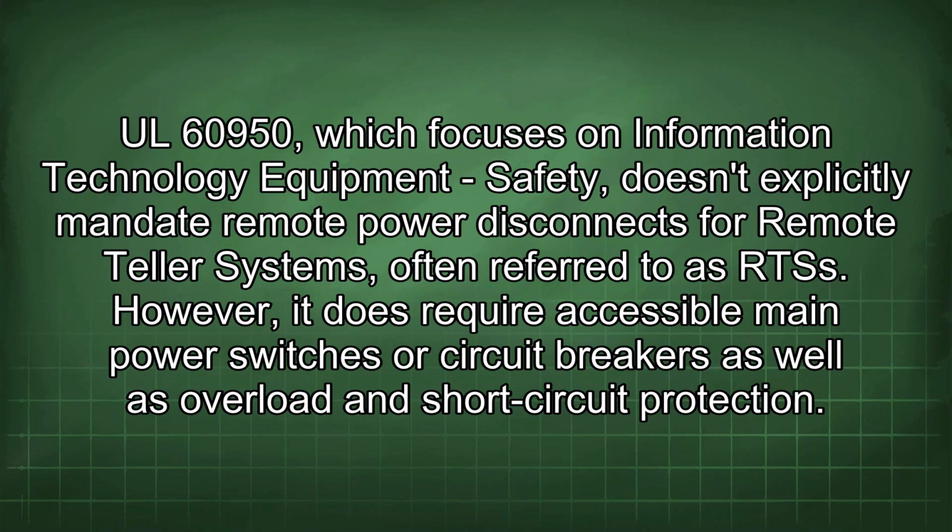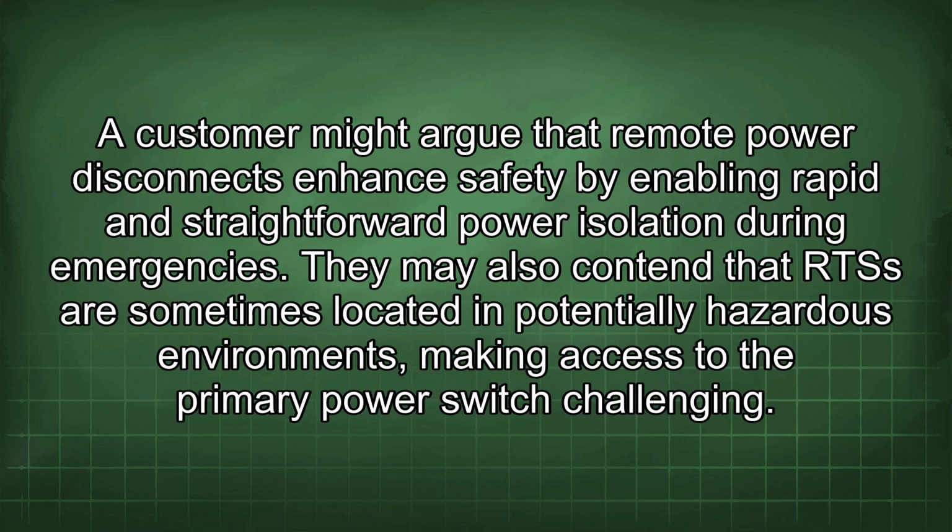UL 60950, which focuses on information technology equipment safety, doesn't explicitly mandate remote power disconnects for remote teller systems, often referred to as RTS. However, it does require accessible main power switches or circuit breakers as well as overload and short circuit protection. A customer might argue that remote power disconnects enhance safety by enabling rapid and straightforward power isolation during emergencies.